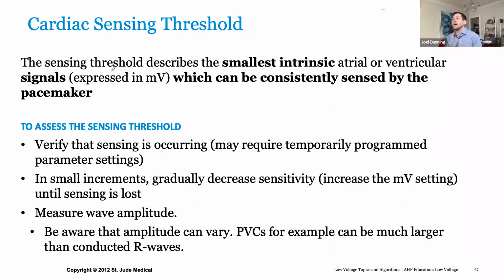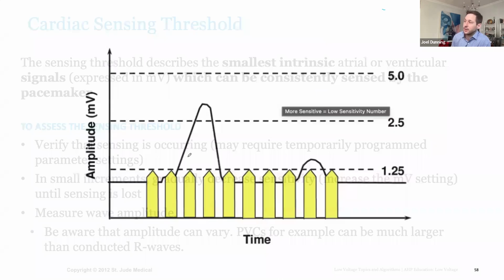So next we talk about sensing and the threshold behind it. Similar to what we talked about with voltage, but the inverse, it's the smallest intrinsic signals that can be consistently sensed by the pacemaker. There's a couple ways you can do that too. The device itself can measure the amplitude of the sensed R wave or P wave, or you can manually decrease the sensitivity, which we'll show here.